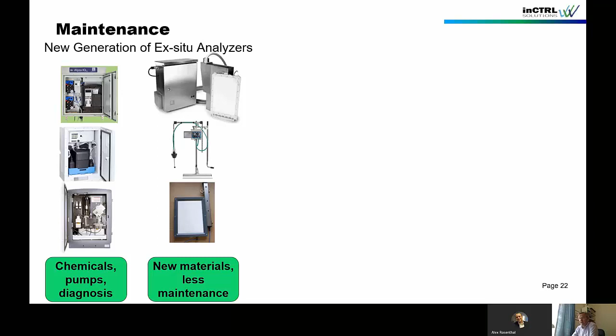Very important is auto cleaning, specifically for the optical probes. There are wipers, air, water, ultrasonic cleaning. My preference clearly is air, most aggressive, so best cleaning results, but I also like the combination of air and ultrasonic because you remove different clogging out of the spectra. Don't forget manual cleaning, and manual cleaning means, at least for the optical probes, cleaning with a brush and then chemical cleaning according to manufacturer specifications. Do that one step after another.